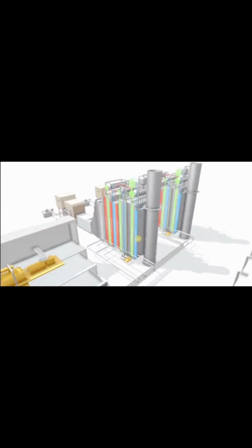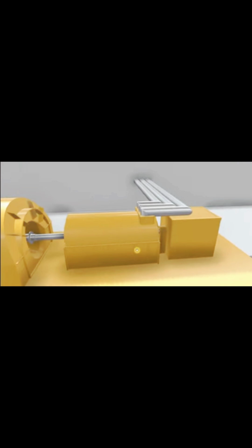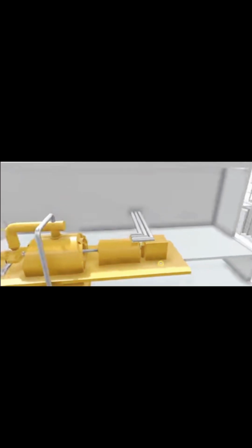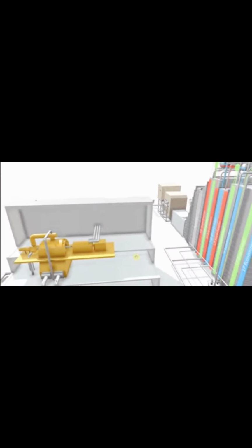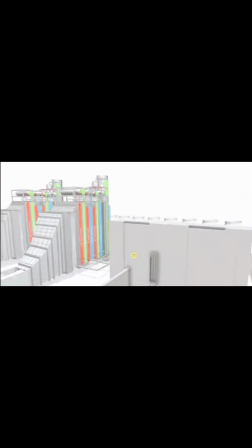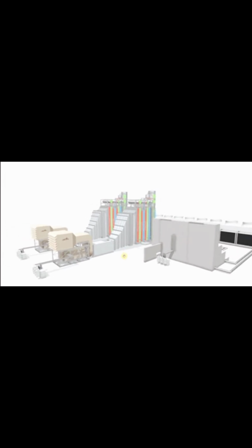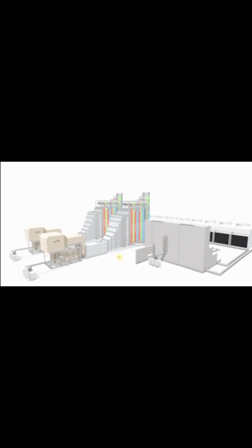The steam from the heat recovery steam generator is sent to the steam turbine, and then the steam turbine rotor rotates and we generate electricity through our generator here. So one heat source which is used to operate both a gas turbine and a steam turbine. When we do that, we have a combined cycle plant and we increase our efficiency, for example, from about 35% potentially, all the way up to 50, 55, and maybe even 60%.